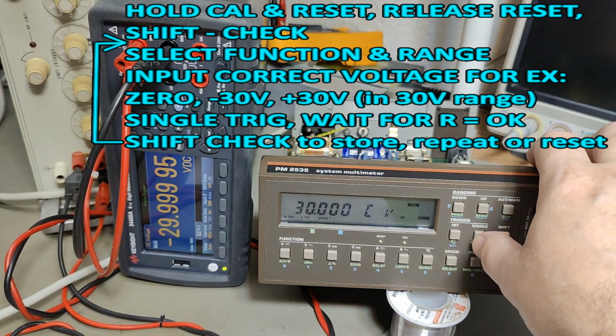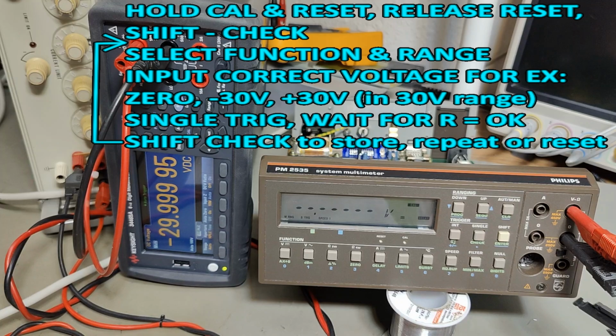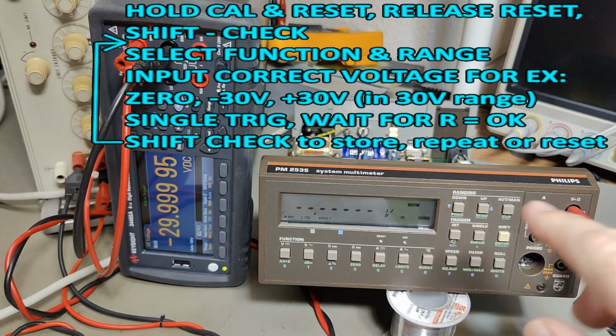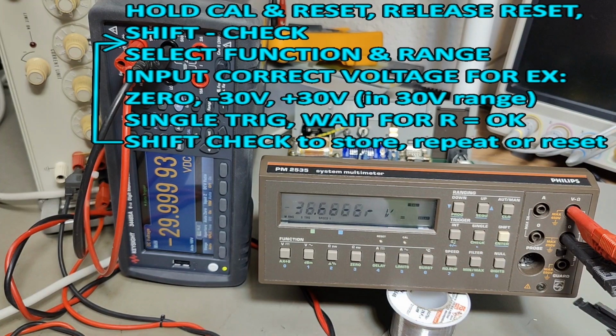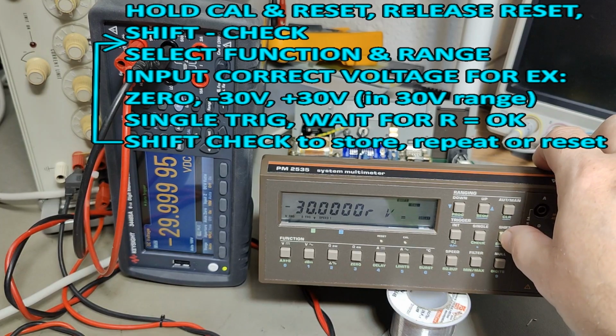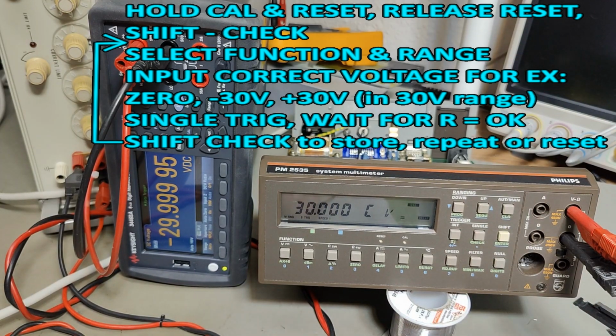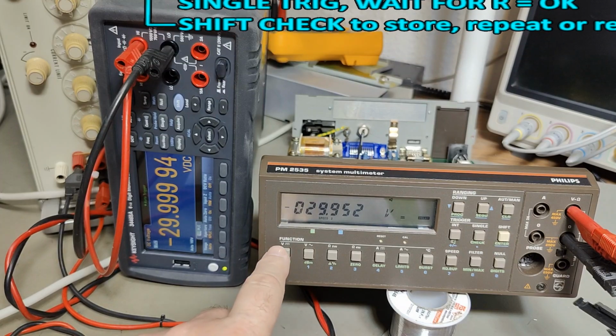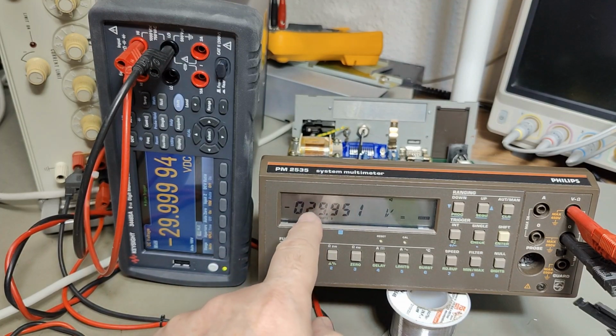And then, okay, single trig the negative 30. And then we should see how that worked out. Of course, after the last calibration here of negative 30, then you have again to store the right value by doing shift check. But I'm waiting for this R. See, here we go. So that was the R, and then shift check. So now I'm done. I've stored those 3 values and I can hit reset. So now the unit is reset. We go back to voltage function, and of course it starts in the 300 volts range.